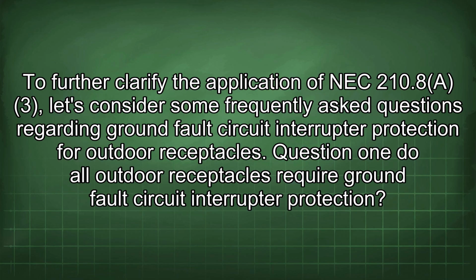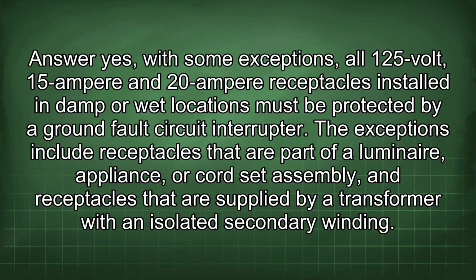To further clarify the application of NEC 210.8A3, let's consider some frequently asked questions regarding ground fault circuit interrupter protection for outdoor receptacles. Question 1. Do all outdoor receptacles require ground fault circuit interrupter protection? Answer: yes, with some exceptions. All 125 volt, 15 ampere and 20 ampere receptacles installed in damp or wet locations must be protected by a ground fault circuit interrupter. The exceptions include receptacles that are part of a luminaire appliance or cord set assembly, and receptacles that are supplied by a transformer with an isolated secondary winding.